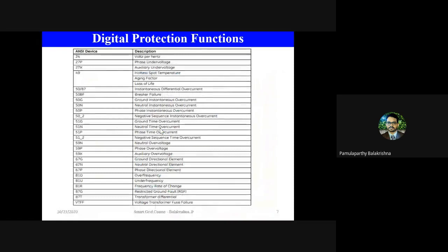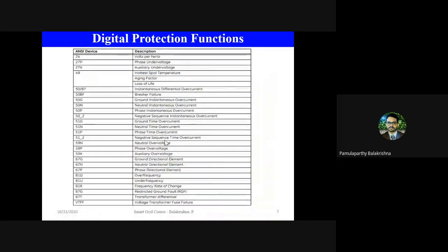Okay, so all these protection functions which I told, which are incorporated in the digital protection relay, have been designed with respect to a reference standard. Okay, so in America we call that the ANSI standard, and in other countries we use IEC standards. So all the protection functions are designed in a standardized manner by adhering to the standards, because irrespective of the manufacturer, like GE or Siemens or ABB, the protection relay behavior should be the same inside the substation. Okay, the way it protects the asset, the way it controls the breaker should not vary drastically.